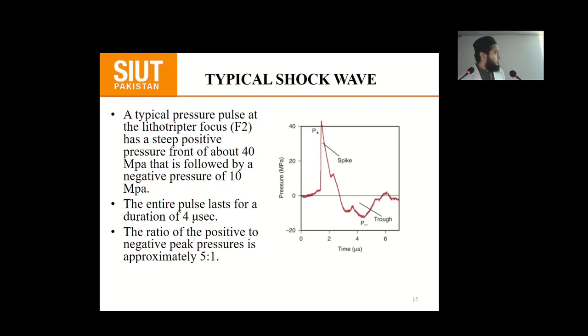So in this picture we can see a typical shock wave. A typical pressure pulse at the lithotripter focus F2 has a steep positive pressure front of about 40 megapascals, followed by a negative pressure of 10 megapascals. This entire pulse lasts for a duration of 4 microseconds, and the ratio of the positive to negative peak pressure is approximately 5:1. Keep in mind that we are discussing the point F2. F2 is the point at which the stone is focused in the kidney, and the initial peak pressure is a steep positive pressure of 40 megapascals, followed by a negative pressure of minus 10 megapascals, and the duration of this pressure wave is about 4 microseconds.